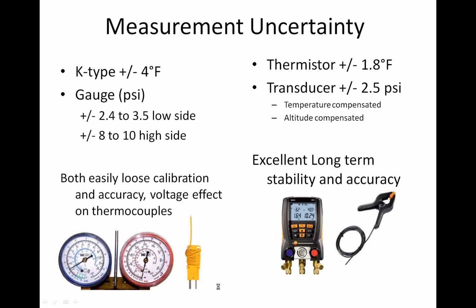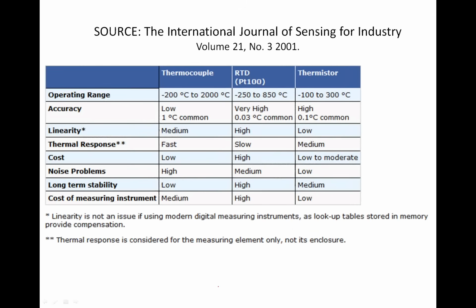Now, I don't like just pulling statistics out of the air and having you believe me. And I just wanted to show you here, and this is from the International Journal of Sensing for Industry, Volume 21, 2001: thermocouples have low accuracy. 1 degree C is common. They have noise problems, high noise problems, and they have low long-term stability.